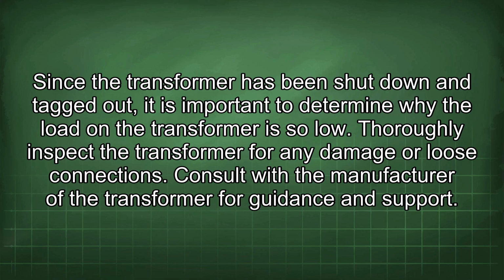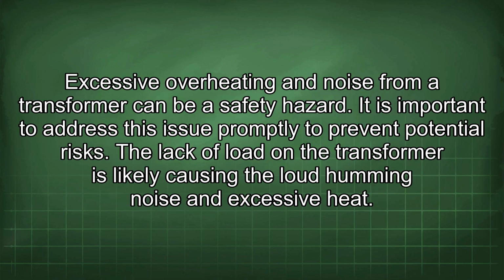Consult with the manufacturer of the transformer for guidance and support. Excessive overheating and noise from a transformer can be a safety hazard. It is important to address this issue promptly to prevent potential risks. The lack of load on the transformer is likely causing the loud humming noise and excessive heat.